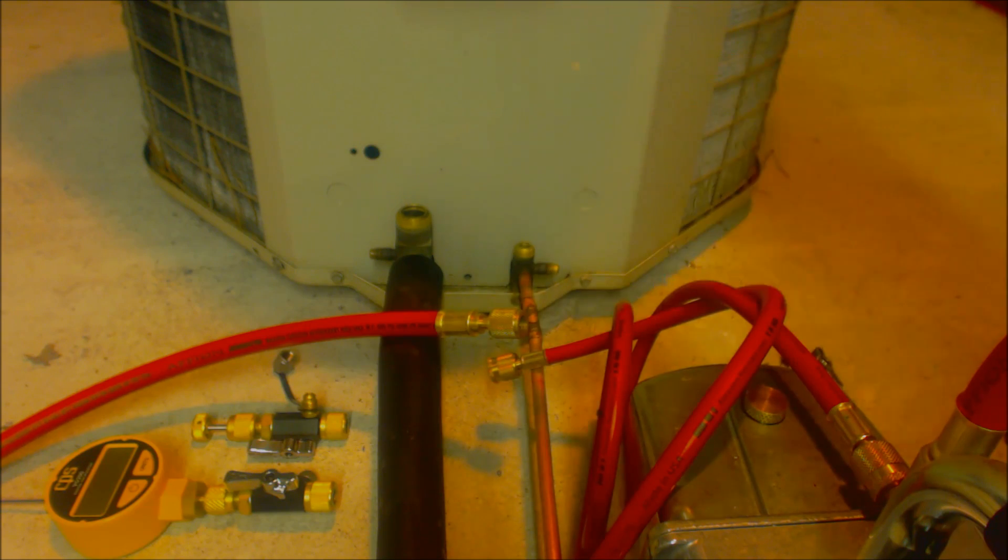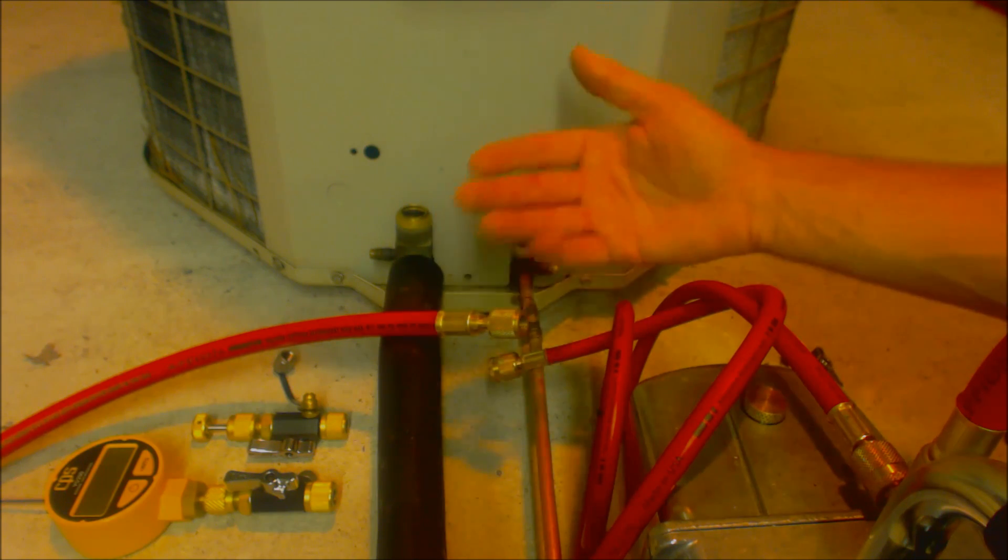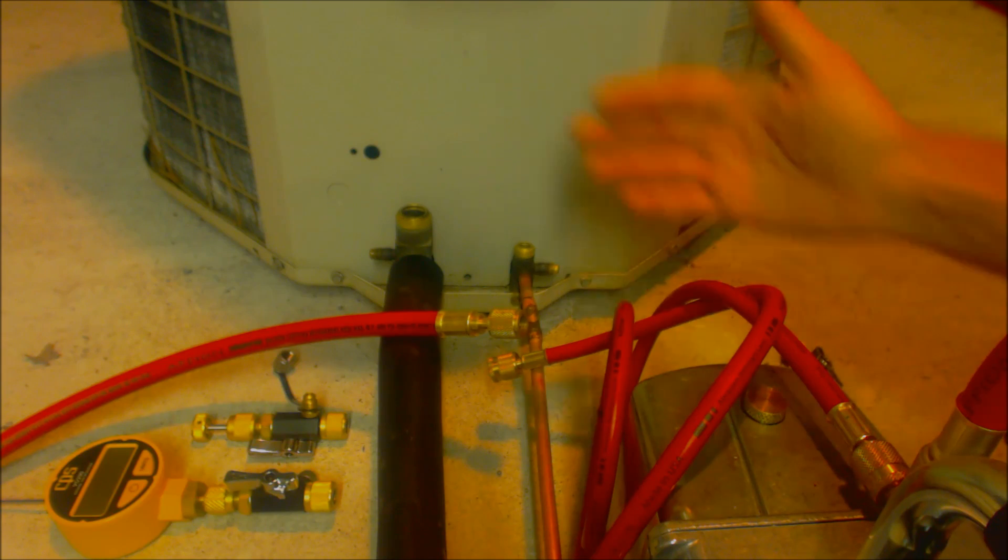This vacuum will be done after the brazing and after the pressure test. Part of the line set or the evaporator coil may be existing, so it may have oil in it. In that case you want to do an oil blowout after the pressure test. If it's a whole new system you do not need to do an oil blowout. You can check some of the other videos I have in the playlist for nitrogen pressure testing and oil blowouts.